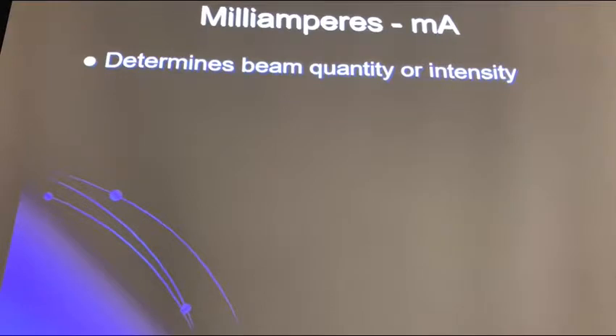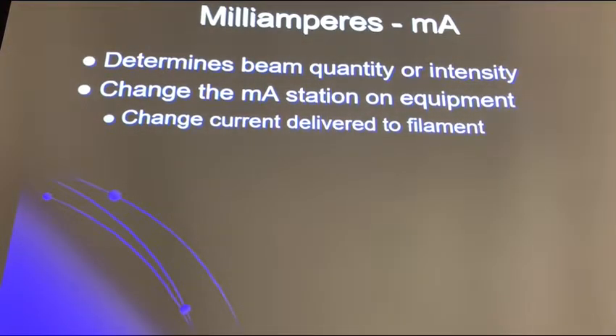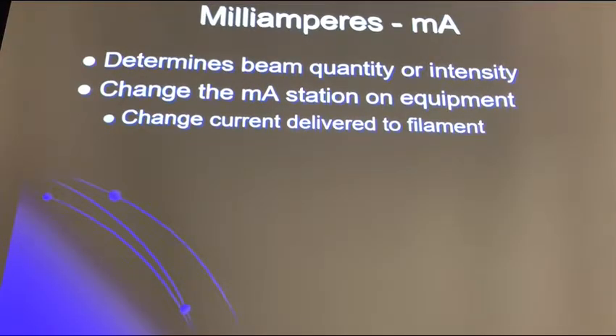Milliamperage (MA) determines beam quantity or intensity. Changing MA stations on equipment changes the current delivered to the filament. For example, when you go from the 100 mA station to the 500 mA station, you're changing how much current can flow — think of it like bigger, thicker wires that can move more current.